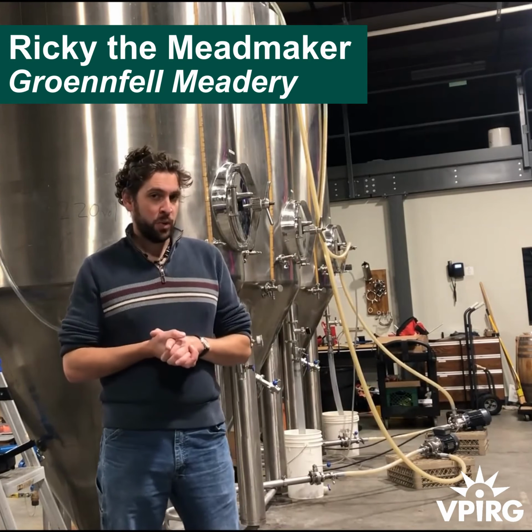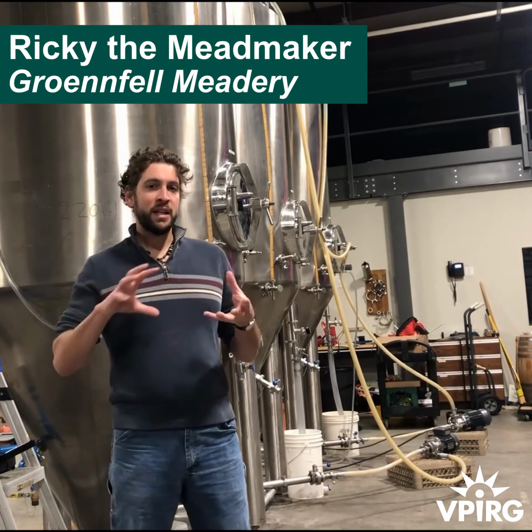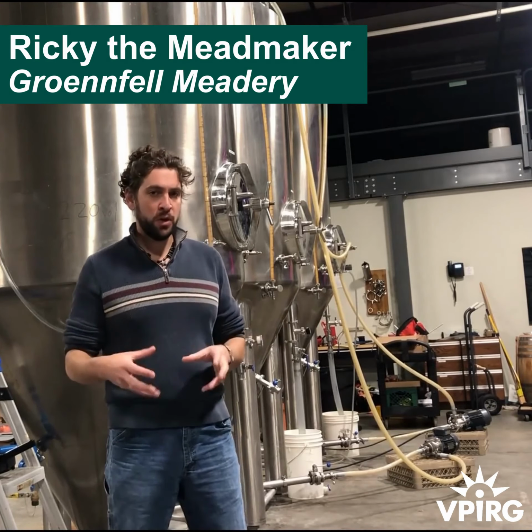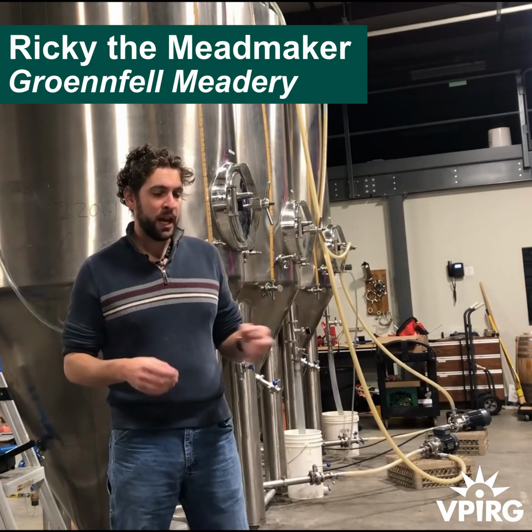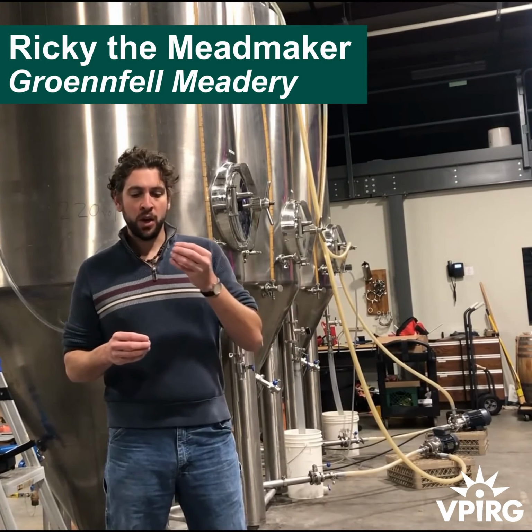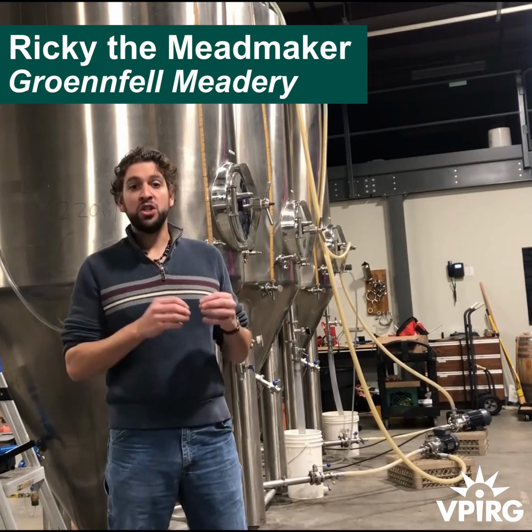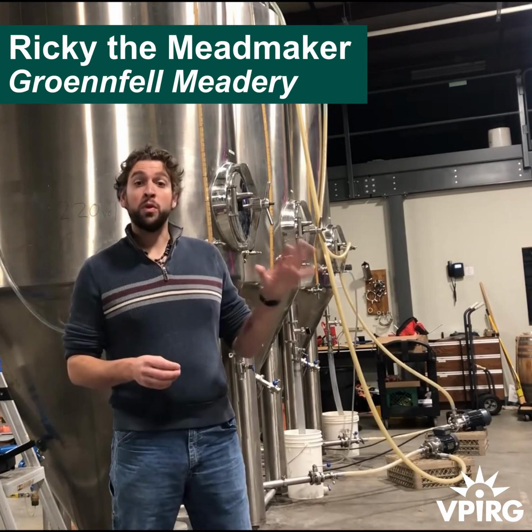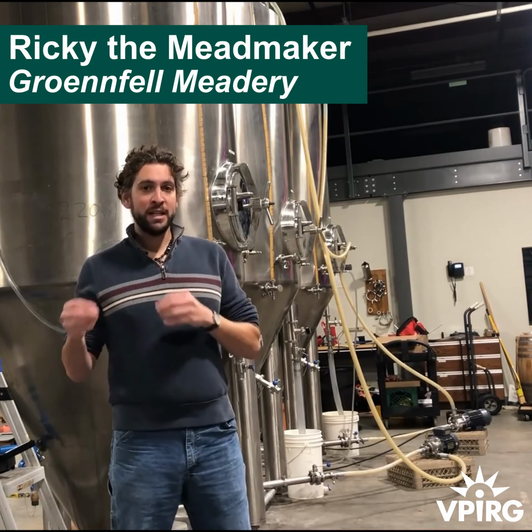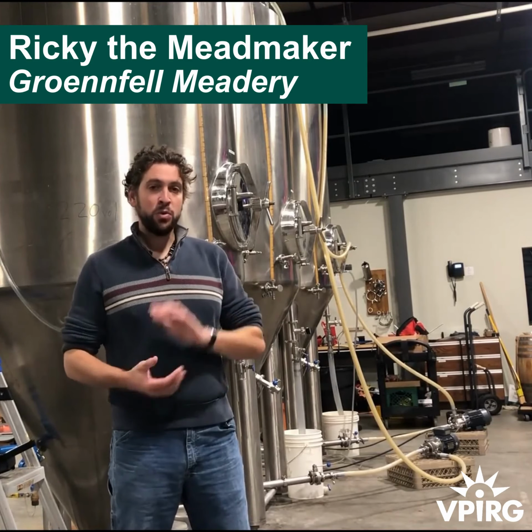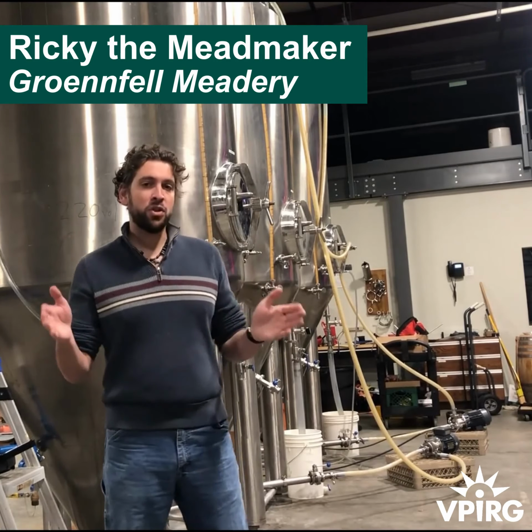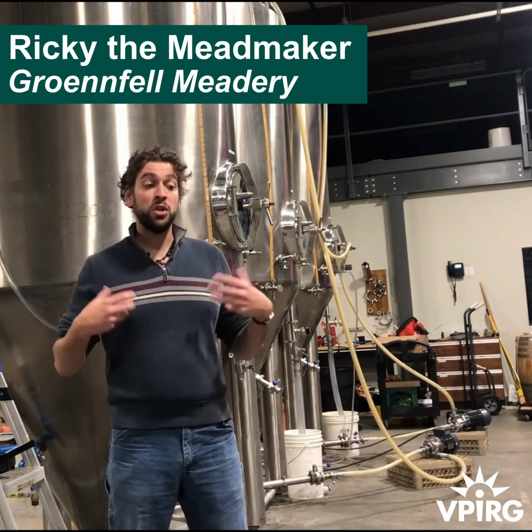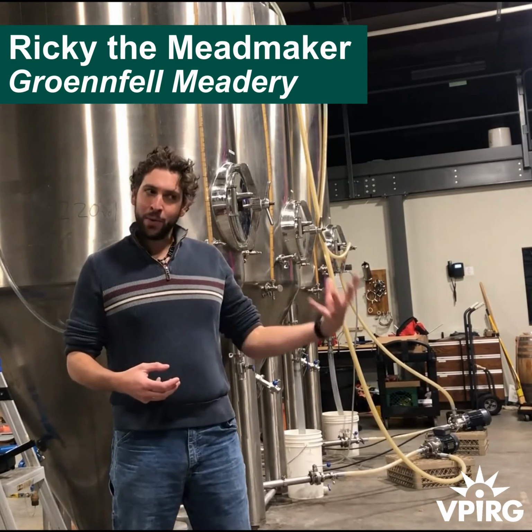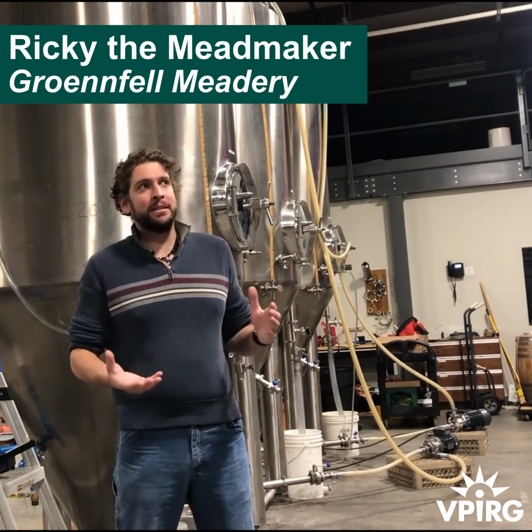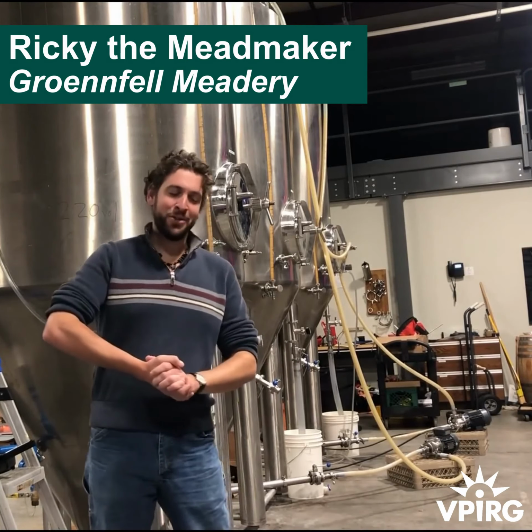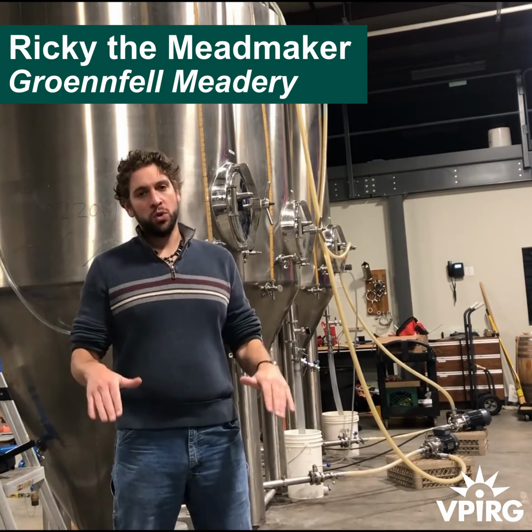The big innovation we have here is a timer built into our computer, which is harder than it sounds. What it can do is coordinate with our brew staff to check for peak usage through Green Mountain Power. So we can tell our tanks, yes, you need to cool, but if it's during a peak period of usage, which usually calls up power supplies that are, we'll just say dirty, not to get in trouble with anyone in particular, don't turn on.